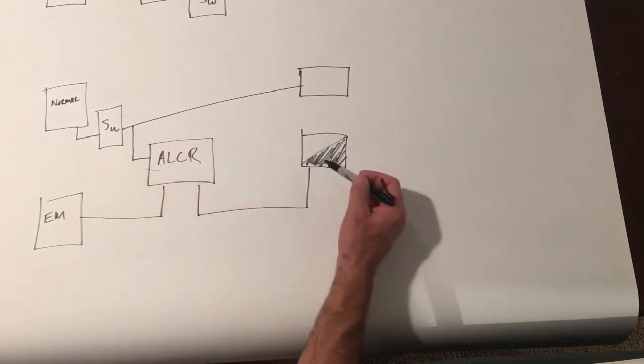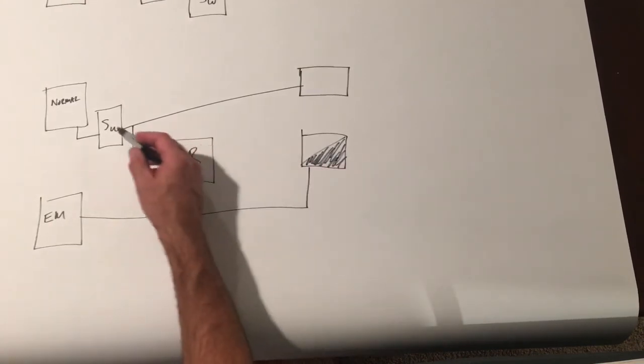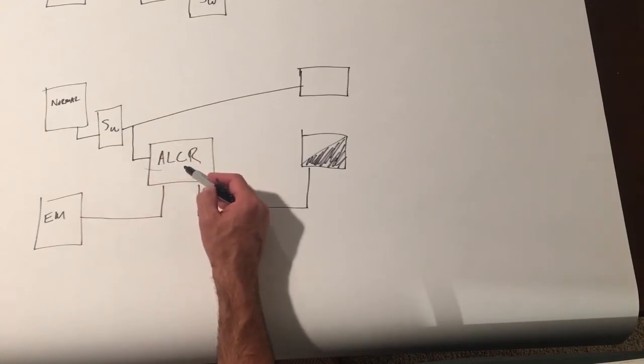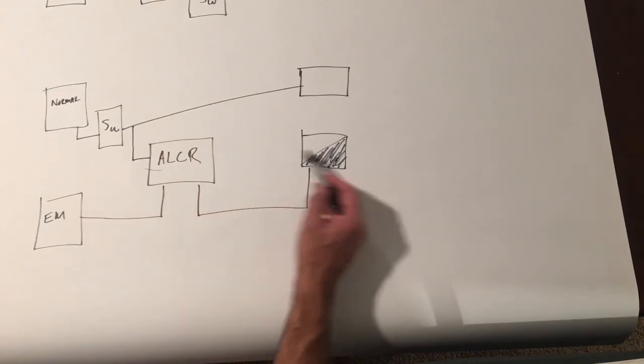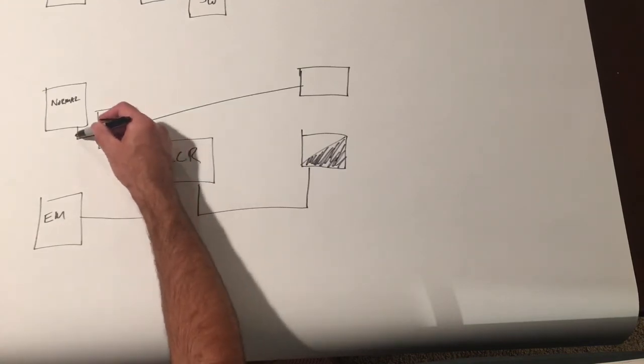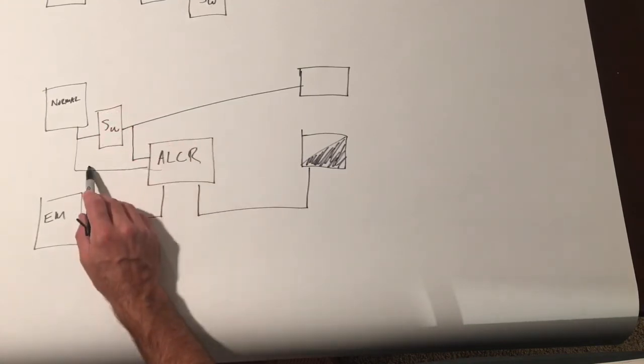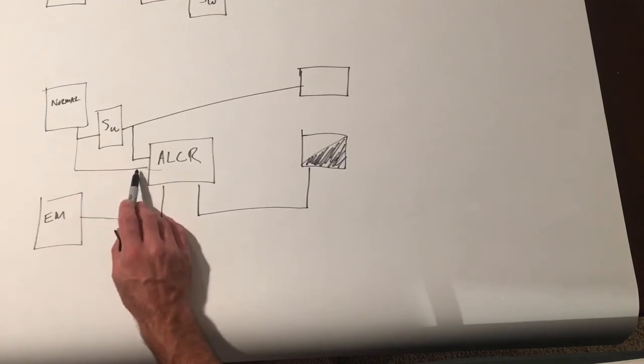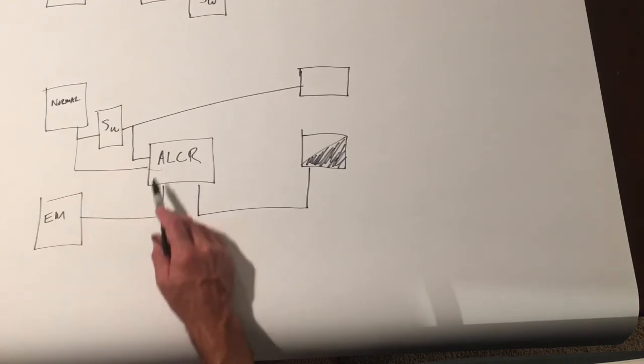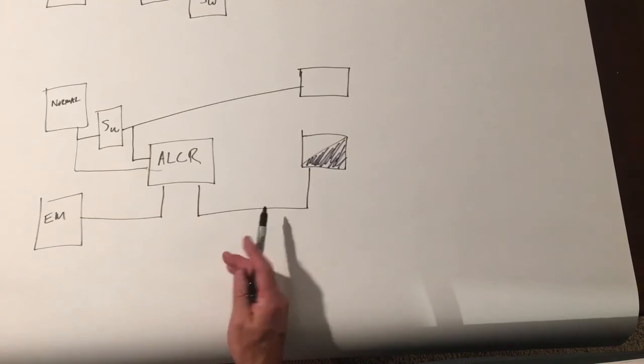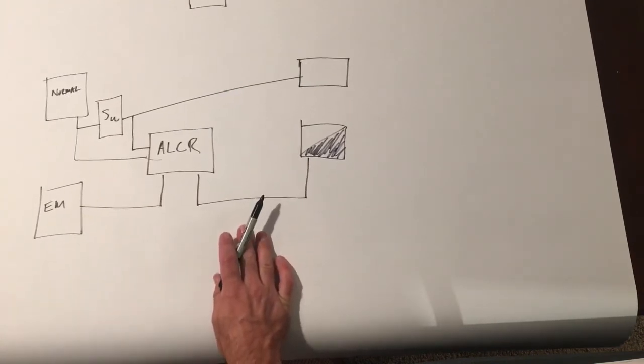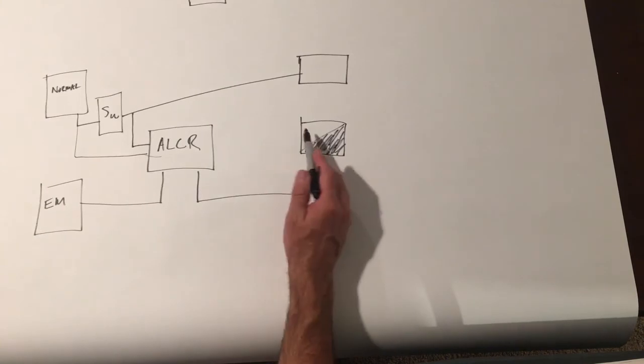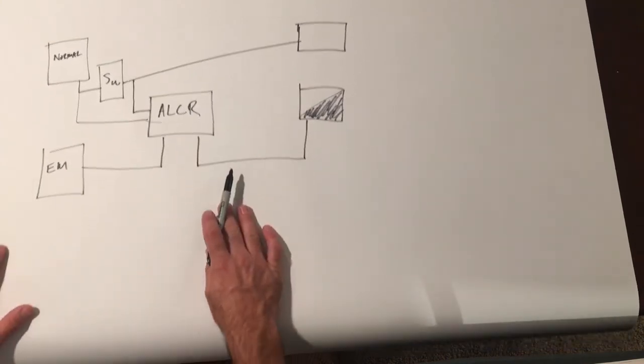If it's off, power, this lights off. So it's actually this is telling the automatic load control relay what to do to have that fixture, but it's always powered by emergency. And we also have unswitched normal, which when this goes away, tells this to turn on regardless of the switch position. So that's how we do it. So now we control 10 fixtures, nine normal one emergency with the automatic load control relay.